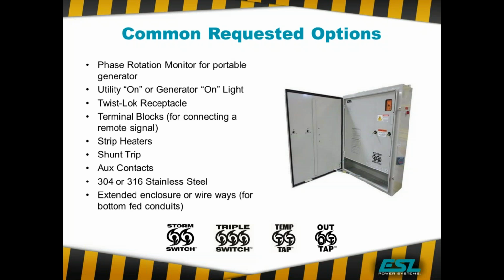We can put shunt trips on the breakers to open them up with an automatic signal. Again, this is going to come into play when we talk about load bank testing and the importance of being able to provide shunt trips. The aux contacts are also on the breakers, so you can monitor the position of the breakers and send certain information with certain breakers to remote locations.